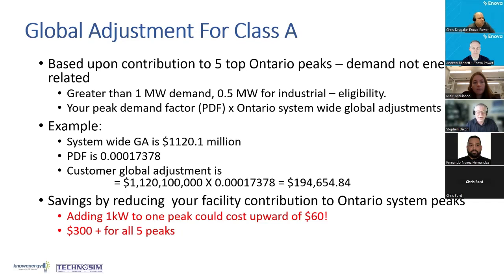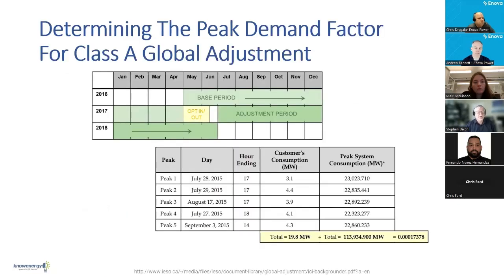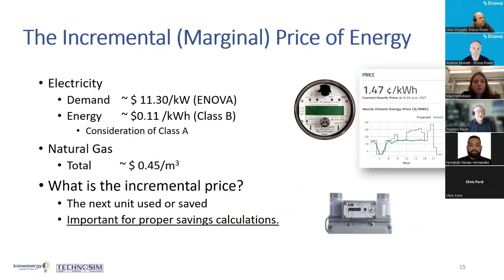At 10 cents a kilowatt hour, that's about $900 a year. But that 1 kilowatt will take away $300, because you take a kilowatt off each of those 5 top peaks. That's lucrative, right? So a lot of people try to shoot for that peak, but you can actually take it off the bottom as well. So again, knowing what you're paying for and what it's worth is very important.